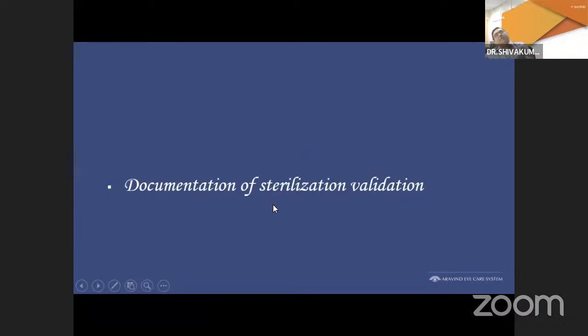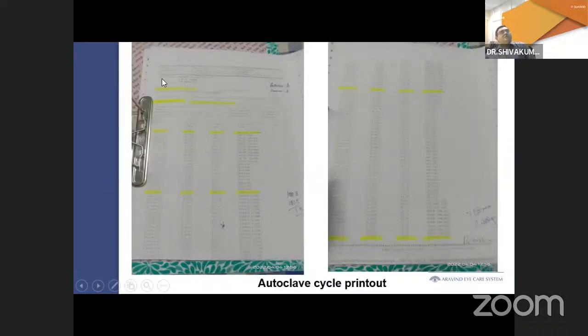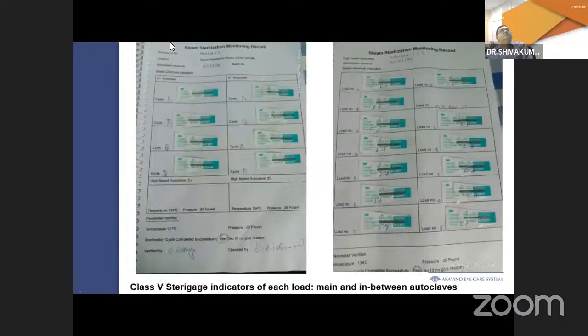Now, documentation of sterilization validation is probably the most important when it comes to finding out deficiency in sterilization. So here is the printout from the automated autoclave, and you can see that the different cycles have been marked out. And the operator has checked whether the minimal temperature is above 121, and whether the fluctuation between the highest and the lowest temperature is within 2 degrees centigrade. It is signed by the operator and countersigned by the CSSD in charge. This is a register containing the steam sterilization monitoring.